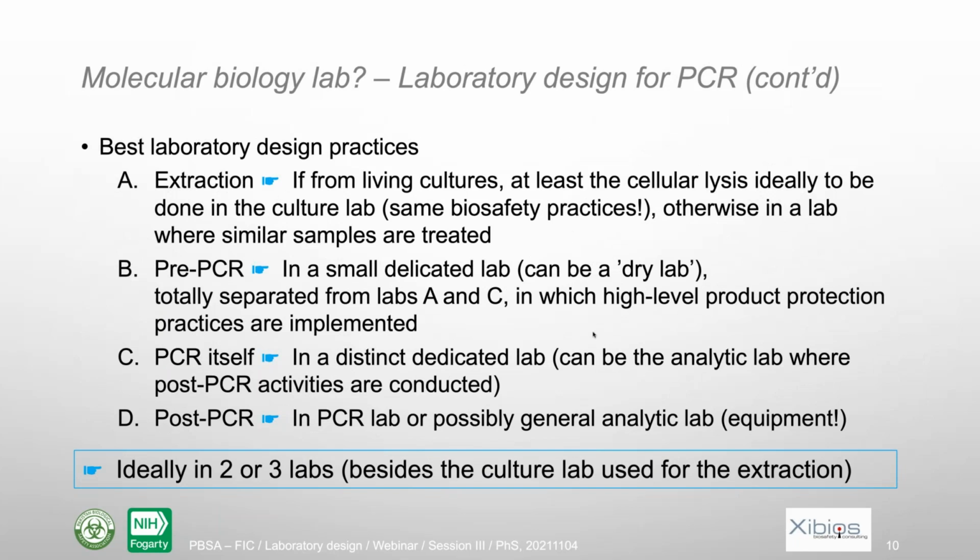So with respect to laboratory design, the best practice would be to separate all that. First, the extraction. If it is from living materials, from infectious materials, at least the first step, the cellular lysis, should be done in the cell culture lab, where there are biosafety practices in place. In that case, you avoid bringing any biosafety issues into the other labs.